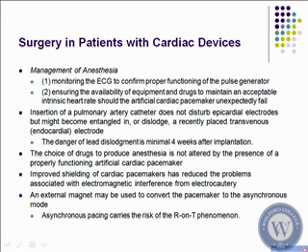Monitor the EKG for proper functioning of the pulse generator, ensuring the availability of equipment and drugs to maintain an acceptable intrinsic rate. Okay. Be careful inserting PA catheters, as you may actually disturb epicardial electrodes, but they also may become entangled, which is a very dangerous part. If you become entangled in the wires, do not pull it out. Okay? Nothing worse than doing that because you can actually pull it out of the heart.